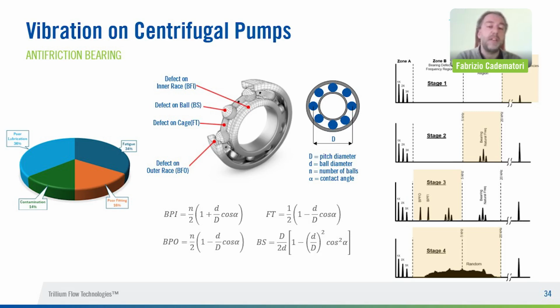At stage 3, readings continue to increase. In addition, specific bearing defect frequencies appear in the spectrum. I put some formulas in this slide to calculate these frequencies, but you can find them in all the catalogs of manufacturers. Stage 4 is the final stage of bearing deterioration before total failure. The discrete bearing defect frequencies disappear and are replaced by random vibration in the form of a noise floor.